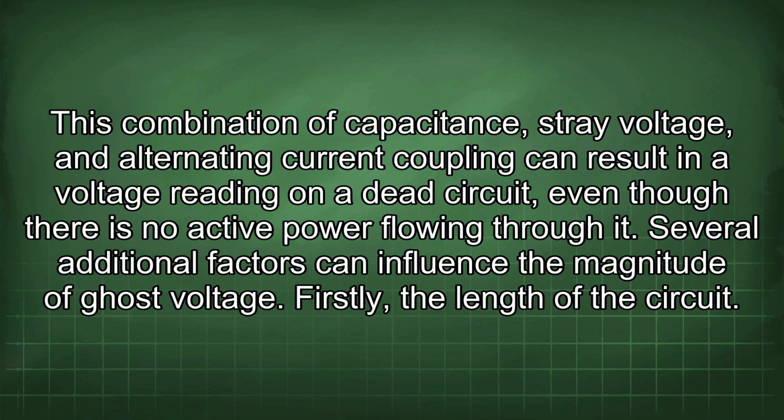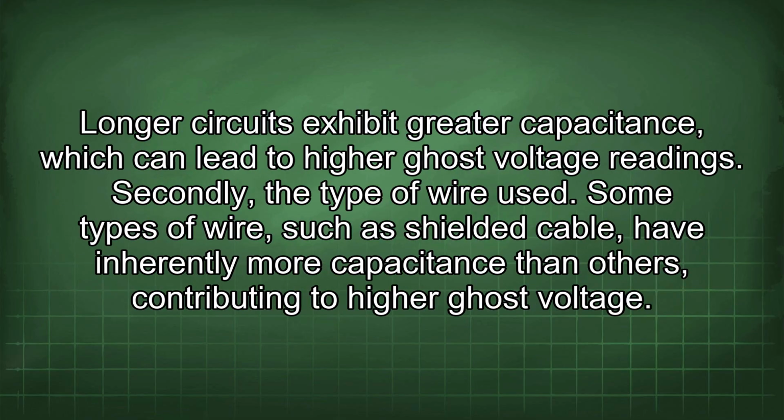This combination of capacitance, stray voltage, and alternating current coupling can result in a voltage reading on a dead circuit, even though there is no active power flowing through it. Several additional factors can influence the magnitude of ghost voltage. Firstly, the length of the circuit. Longer circuits exhibit greater capacitance, which can lead to higher ghost voltage readings.